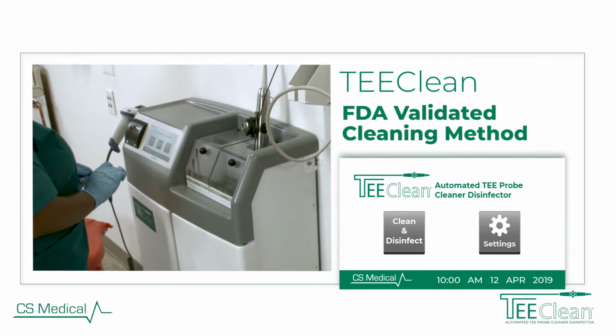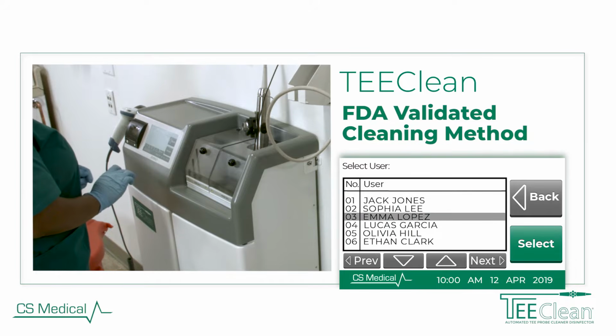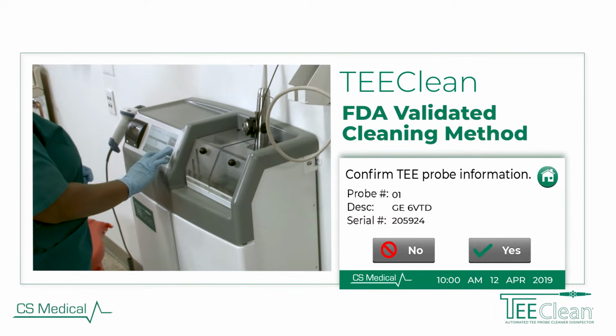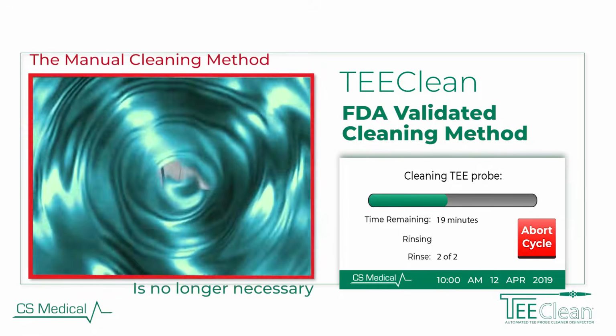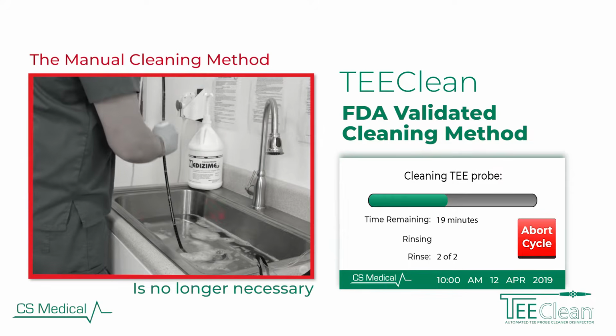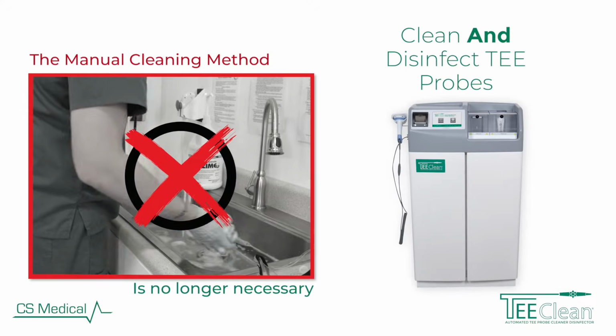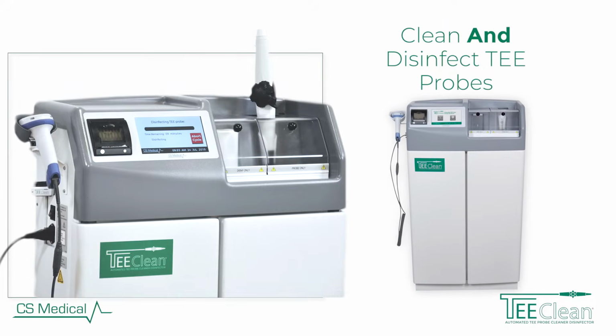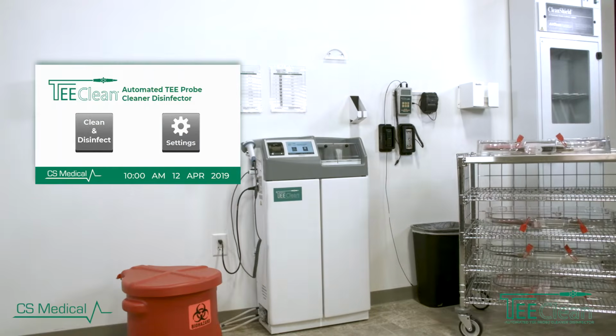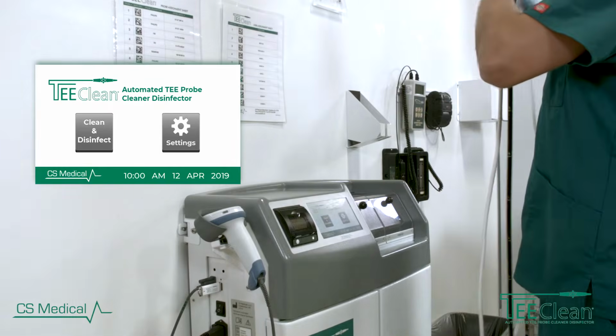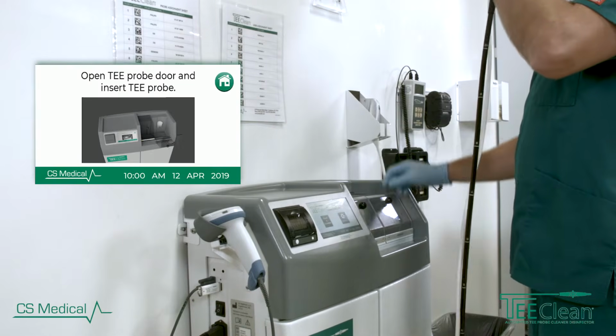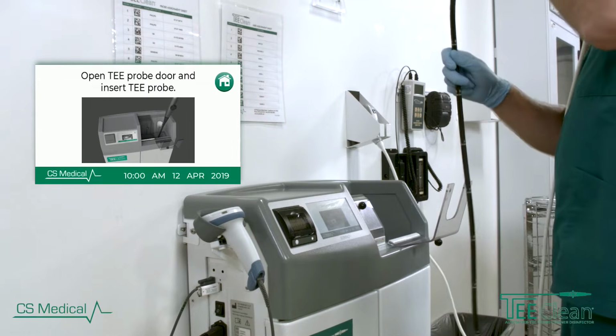TEEClean, an FDA-validated cleaning method, removes the labor and time-intensive manual portion of this process. TEEClean automates the enzymatic soak that has traditionally occurred in a sink or basin. By removing the manual process, TEEClean significantly reduces the handling of the delicate transducer of the TEE probe, thus further reducing the chance for damage.